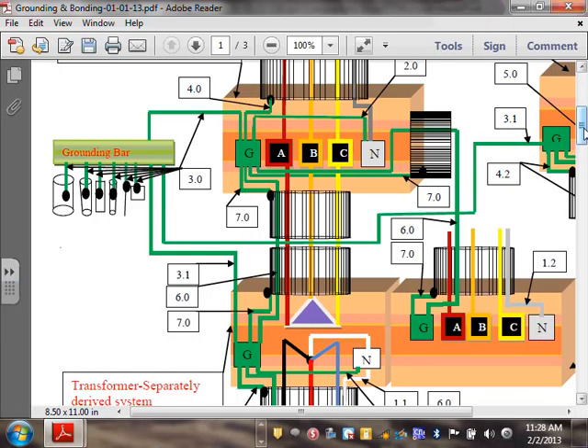Any comment, guys, about number 7 and number 6 here for the separately derived system? Identical, like any other path. Number 6 can be your conduit again, but typically with a transformer, because of vibration, what do we do at the end? Don't you guys flex them? When you flex them, you can't depend on the flex. That's the problem with transformers. When you flex the transformer, you can't depend on the flex. It is not an approved equipment grounding conductor.